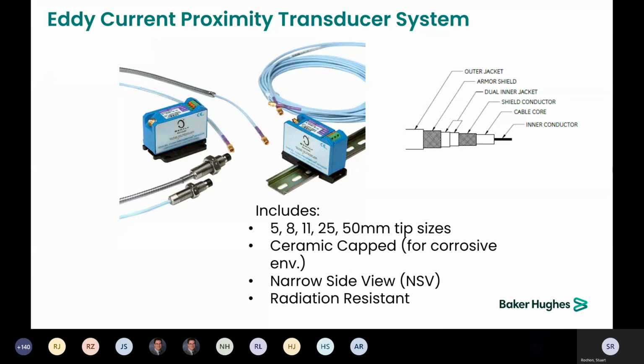And it is, in an event where sensors are paired with different than adequate wire length, is there a way to estimate or calculate the corrected vibration readings? So he's saying, if you have a mismatched system, a set of extension cables and probes. The only way to accurately calculate it is to physically pull it out or set up a similar system on the bench and do a linearity curve, like we talked about, where you put the probe in the bracket and measure every 10 thousandths or 10 mils and see what that comes out to.